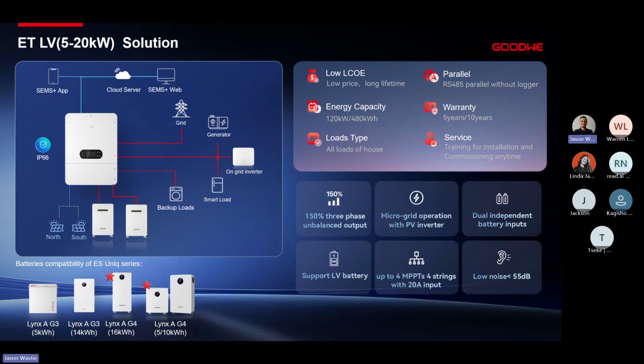What does it mean? On a 15 kilowatt unit, we have 5 kilowatts per phase that we'll be able to output. The 150% three-phase unbalanced output means we can unbalance that, so on phase one, we could have up to 7.5 kilowatts of load. Phase two, maybe we have an additional 6 kilowatts of load, and the remaining load we can then put onto phase three, up to 15 kilowatts total that we'll be able to handle.